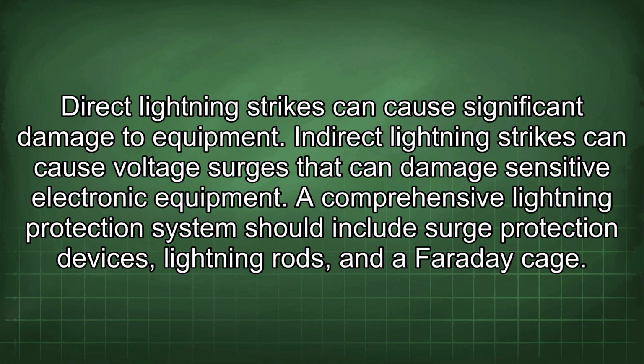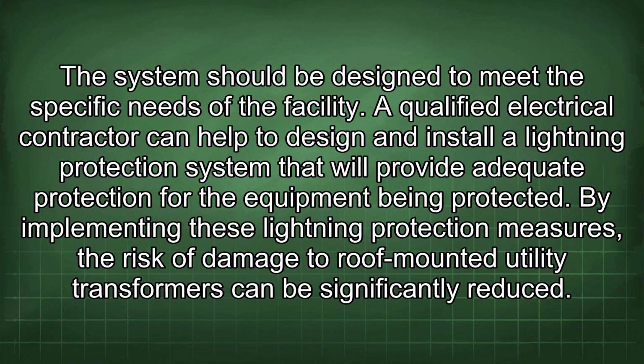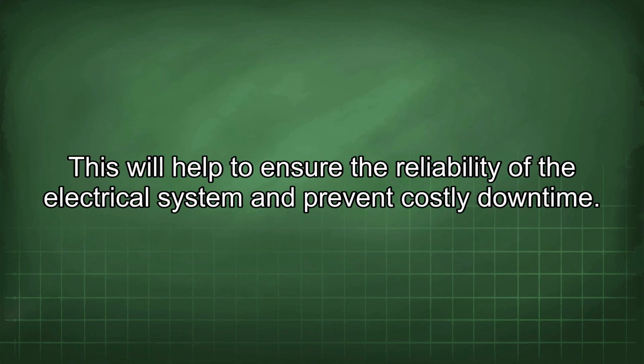A comprehensive lightning protection system should include surge protection devices, lightning rods, and a Faraday cage. The system should be designed to meet the specific needs of the facility. A qualified electrical contractor can help to design and install a lightning protection system that will provide adequate protection for the equipment being protected. By implementing these lightning protection measures, the risk of damage to roof-mounted utility transformers can be significantly reduced. This will help to ensure the reliability of the electrical system and prevent costly downtime.